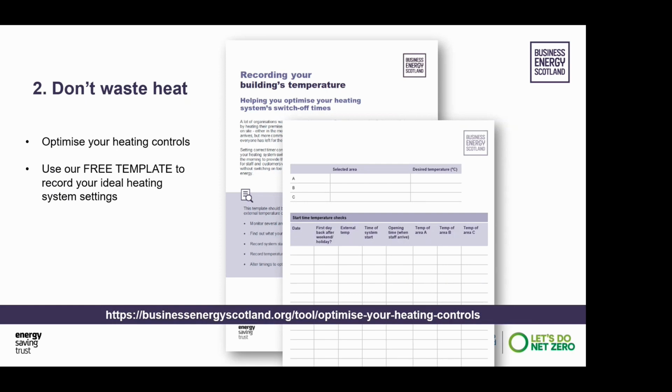Now, the template should be used for a week or two every quarter, or when appropriate in relation to external temperature changes. You can monitor several areas, so different rooms, floors, anywhere where the temperature might vary. You can find out what your desired temperatures are in each of these different zones. You can record system start and switch off times, record temperatures, and then you can alter the timings to optimise your heating system start and switch off times.